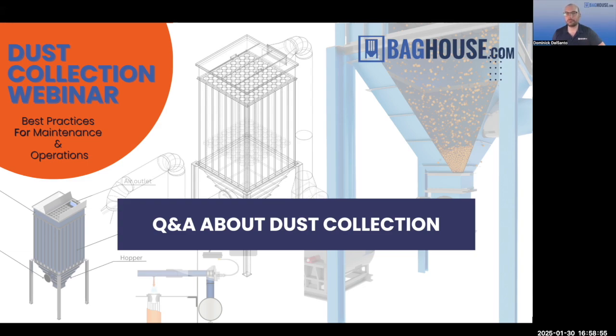They get plugged, the gauges get fouled, and in some places it needs to be monthly, every 2 weeks, sometimes every week, that they need to blow those lines out. And I really like that now we have devices that we sell that are automatic DP line cleaners. My goodness, dude, those save money if you put them in, because every few minutes they shoot air back in to blow the line out. And it saves so much headache.